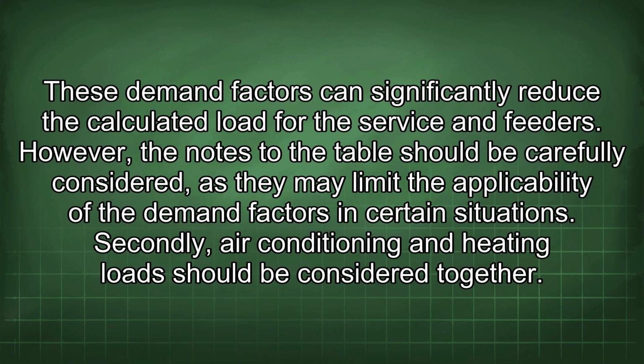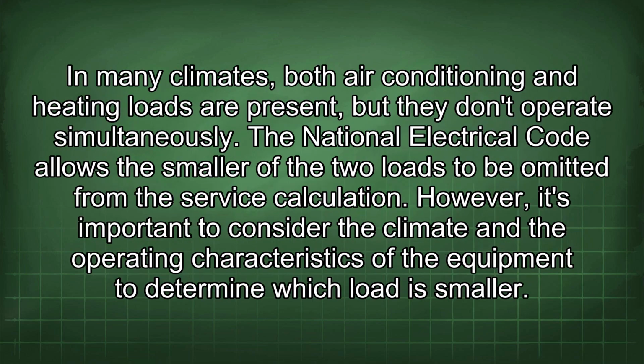in certain situations. Secondly, air conditioning and heating loads should be considered together. In many climates, both air conditioning and heating loads are present, but they don't operate simultaneously. The National Electrical Code allows the smaller of the two loads to be omitted from the service calculation. However, it's important to consider the climate and the operating characteristics of the equipment to determine which load is smaller.